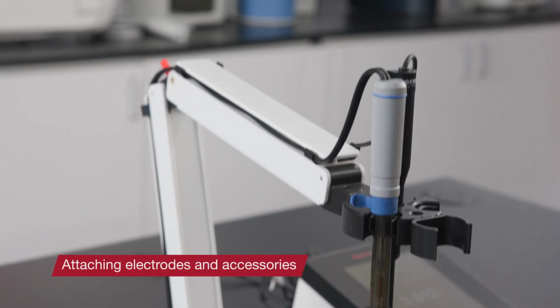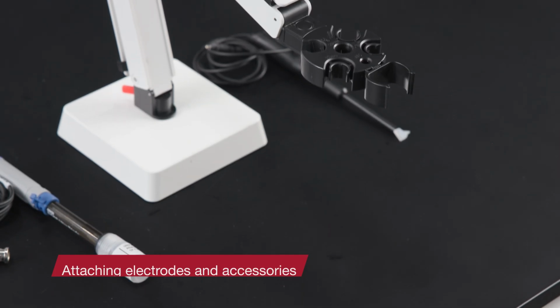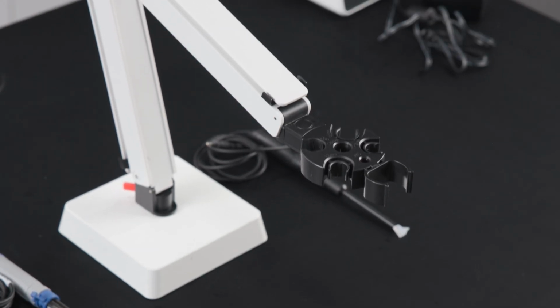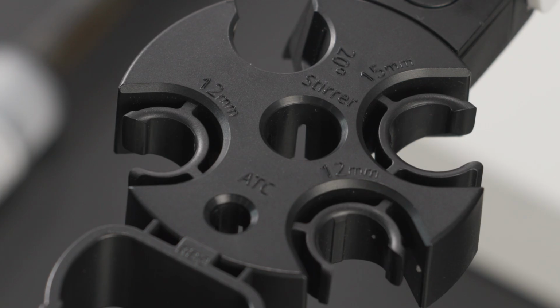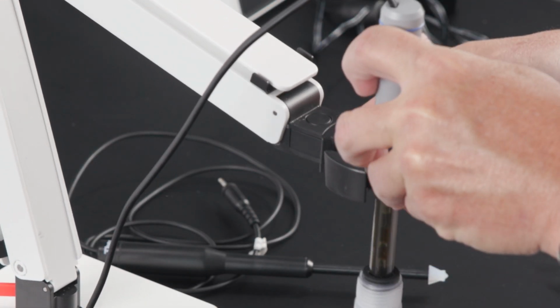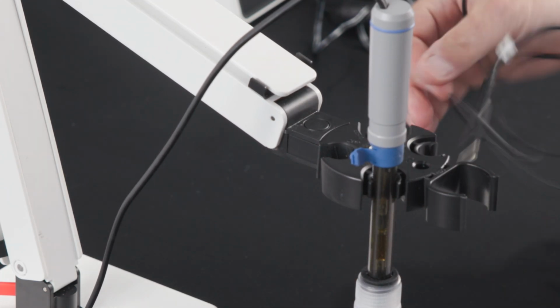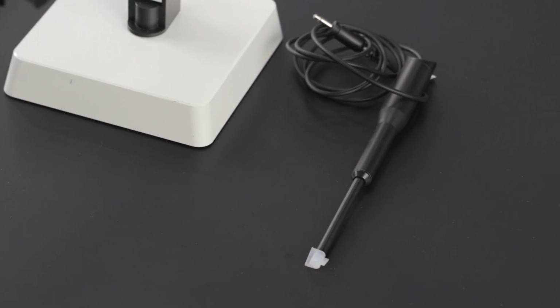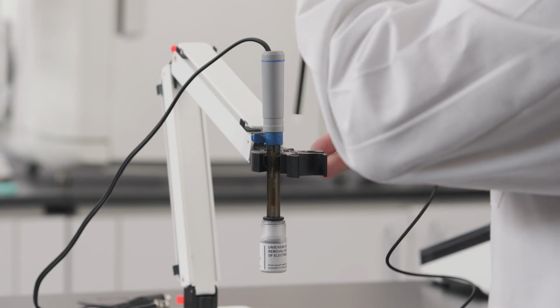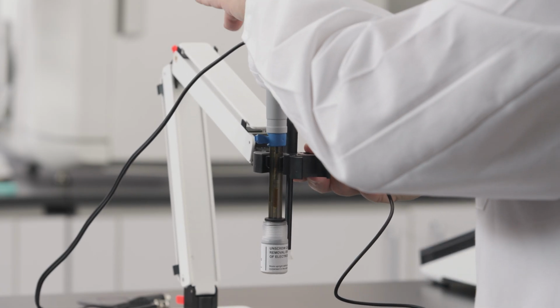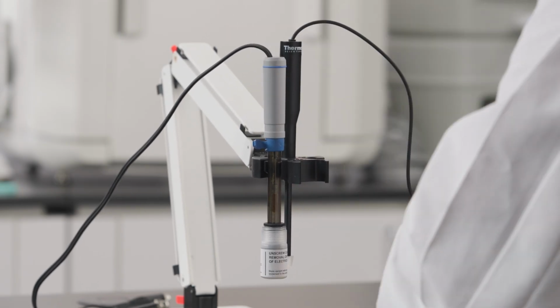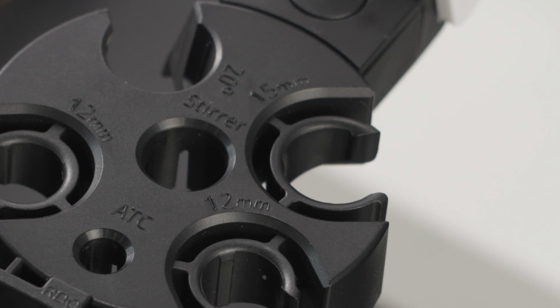The next step is attaching electrodes and other tools to the arm. Orion ProStar meters offer electrode clips to support a range of electrode sizes and types. The recommended electrode diameter for each slot is indicated on the holder. The 12mm clip holds pH electrodes, ORP electrodes, ion selective electrodes, and other electrodes with a 12mm diameter. The stirrer holder is designed to secure the Thermo Orion stirrer probe. As a meter-controlled device, the Orion stirrer probe works seamlessly with Orion ProStar meters. The 15mm clip holds conductivity electrodes, polarographic dissolved oxygen electrodes, and other electrodes with a 15mm diameter.